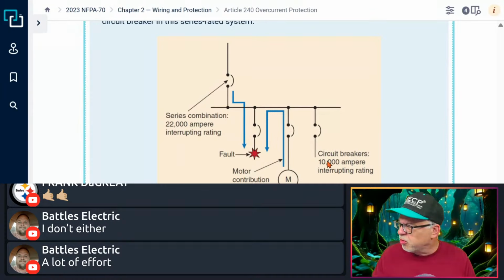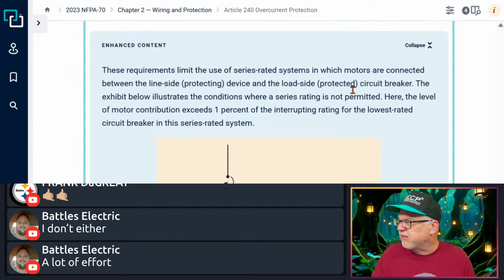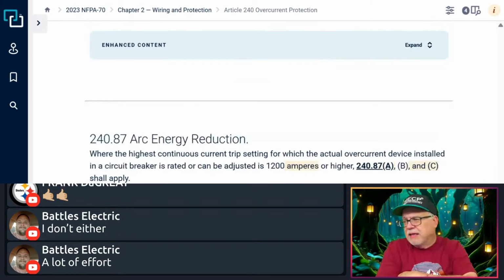So again, we're assuming here that these are all 10,000 amp rated. So any motor in that scenario can't be greater in amps, FLC, than 1% of the interrupting rating of any of the circuit breakers, and all these circuit breakers are 10,000. That's just kind of an illustration. Unless it's really big equipment, I'm pretty sure that when you're dealing with large motors the AIC rating is going to be far greater than 10,000. So it's pretty much going to take care of itself, especially with motor control centers and the different devices. Typically the designers are going to take care of that, but it's still good to know, and it's a low-hanging fruit type of exam question.